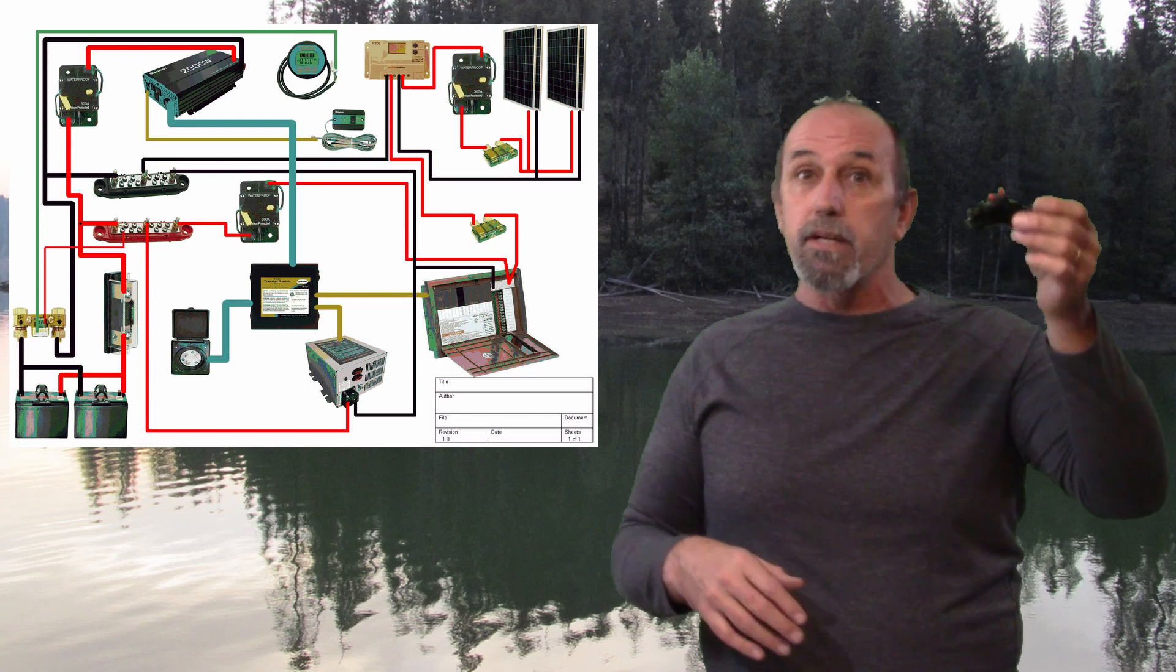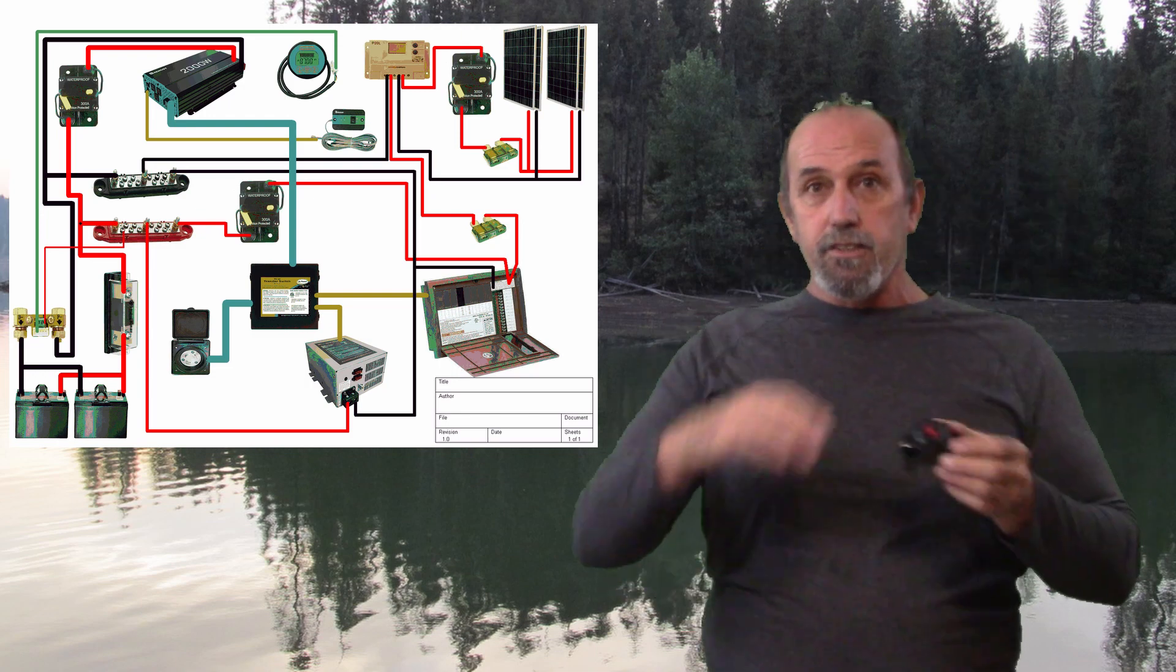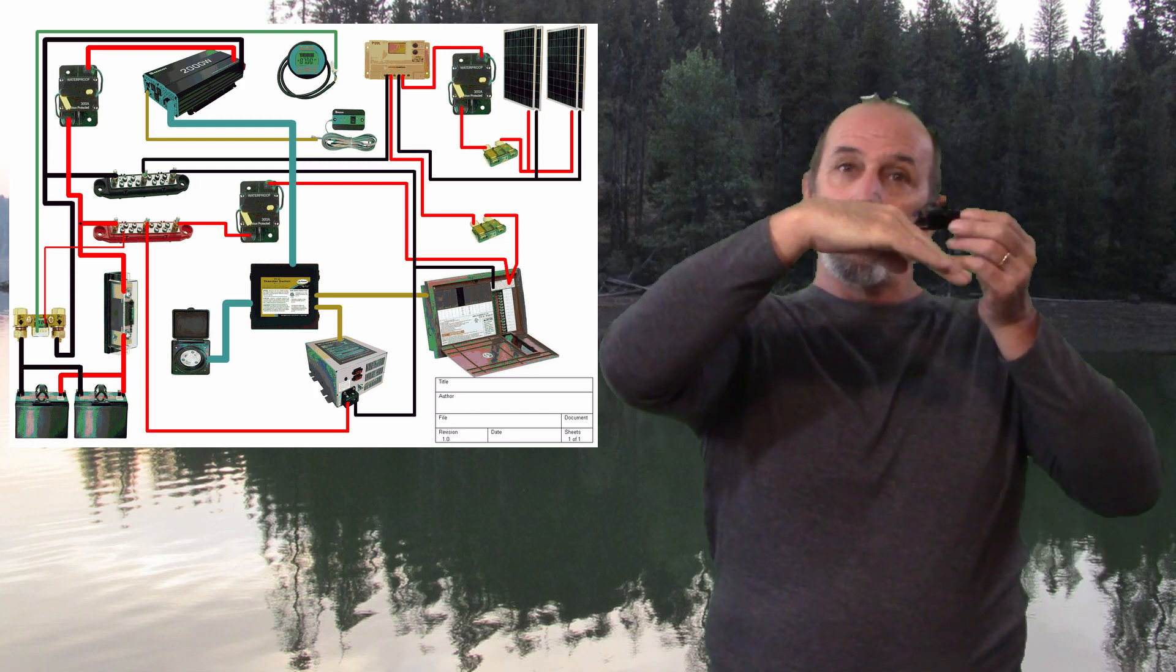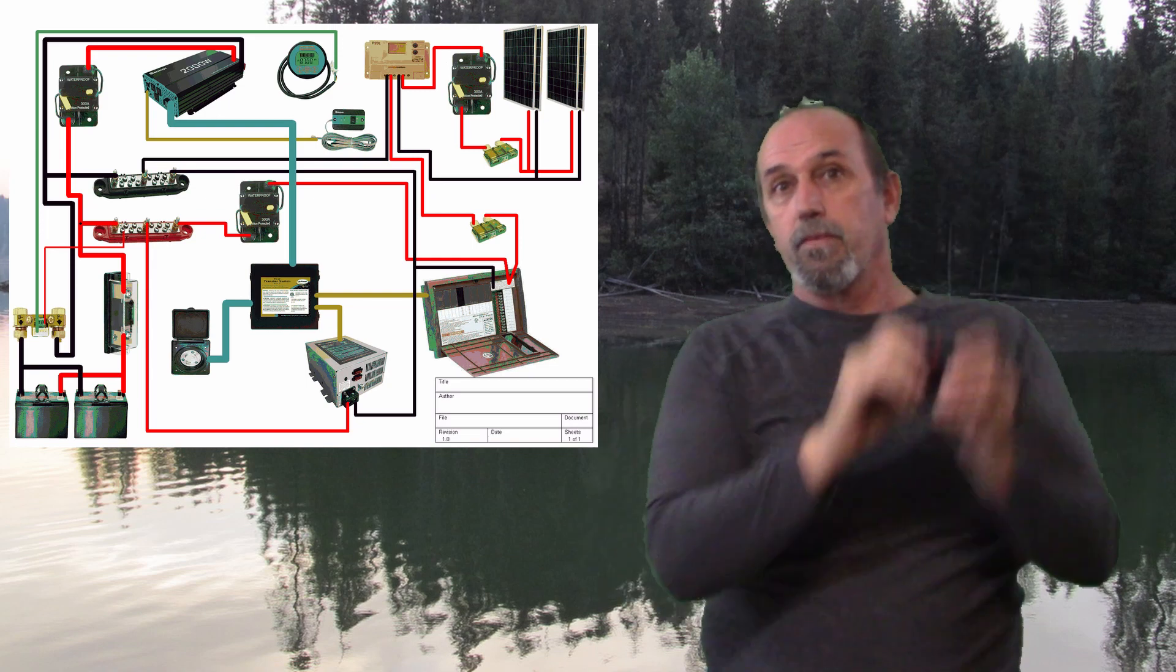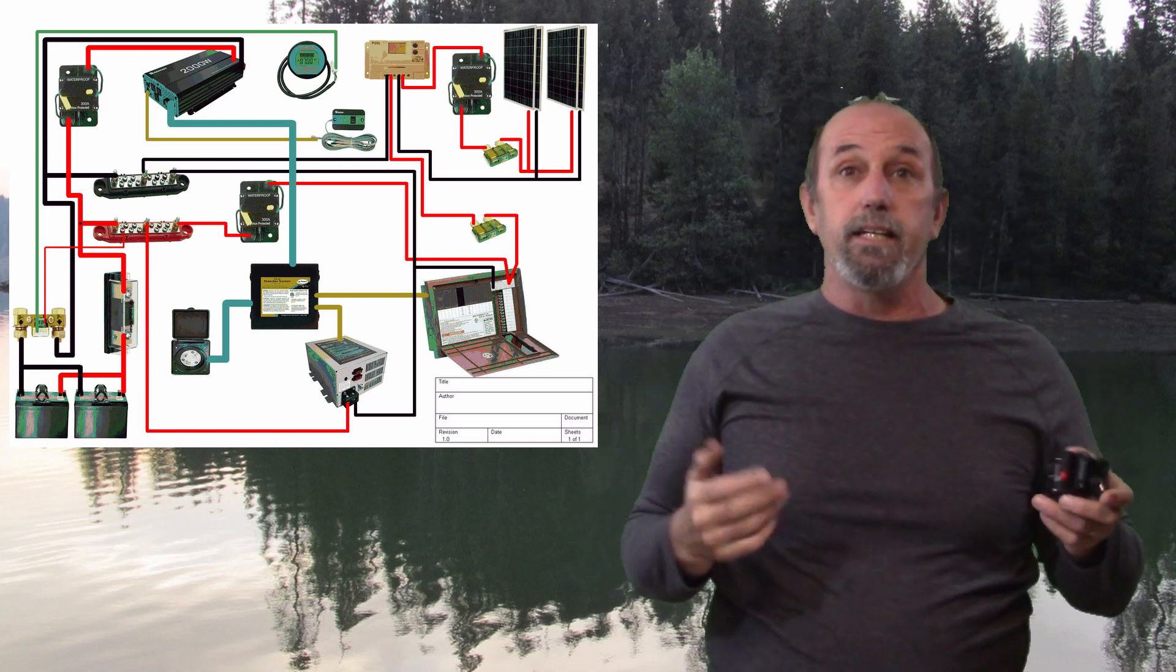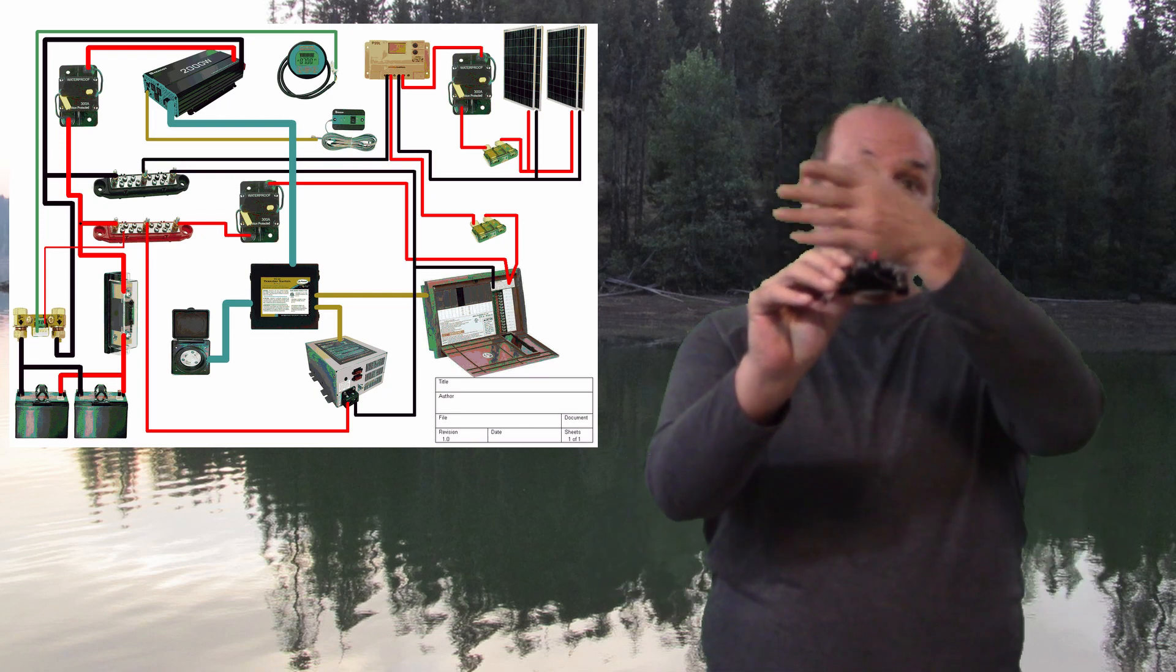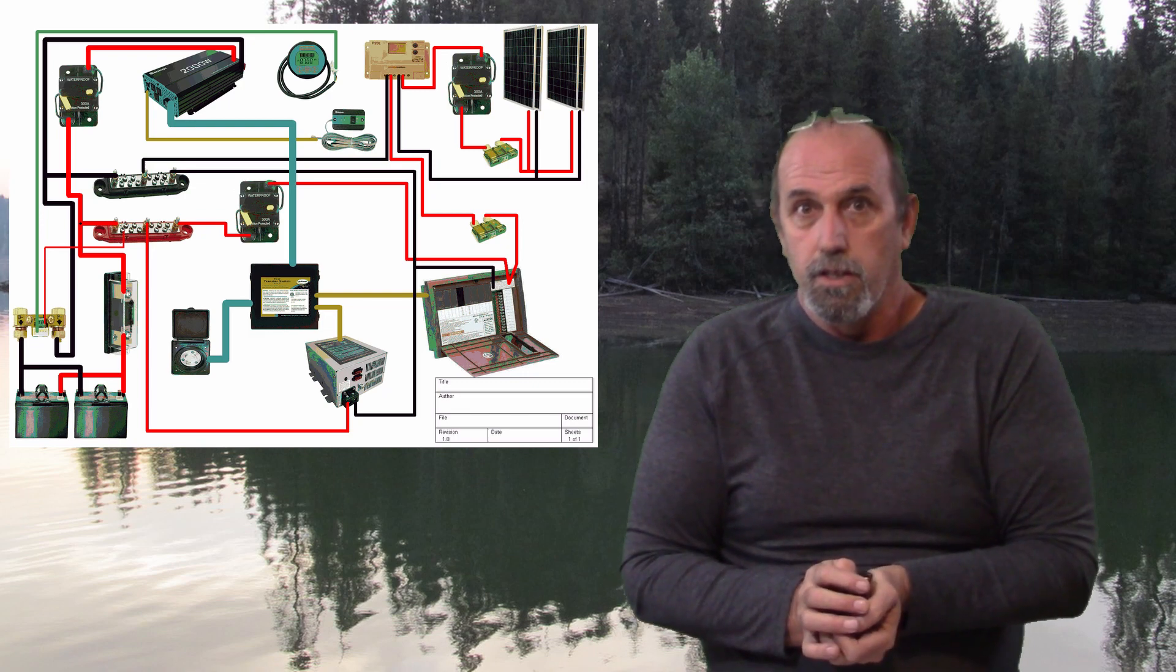This right here has got a bi-metal material inside that actually expands at a different rate. So it actually will move, flex. And when it flexes, it will pop and trip the breaker. And how it does that is by heat, and that's the heat generated by amps going across the material.